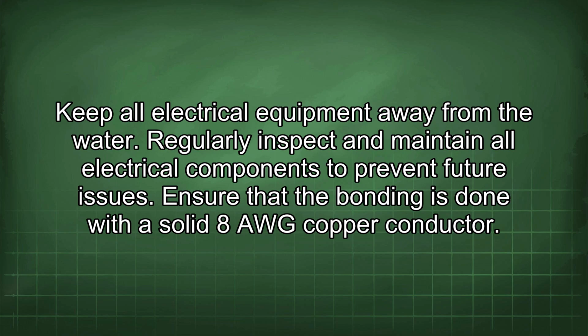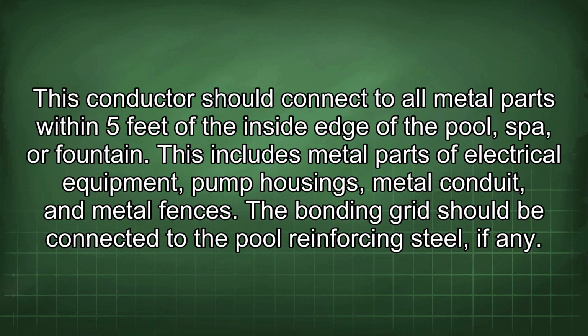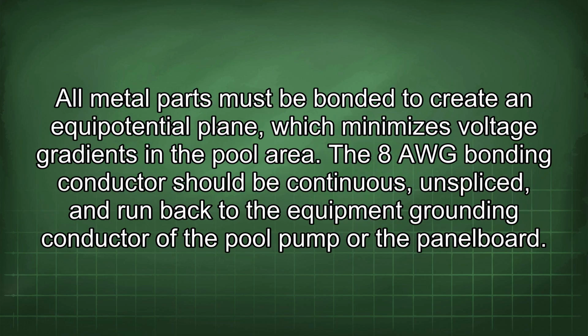Ensure that the bonding is done with a solid 8 AWG copper conductor. This conductor should connect to all metal parts within 5 feet of the inside edge of the pool, spa, or fountain. This includes metal parts of electrical equipment, pump housings, metal conduit, and metal fences. The bonding grid should be connected to the pool reinforcing steel, if any. All metal parts must be bonded to create an equipotential plane, which minimizes voltage gradients in the pool area.